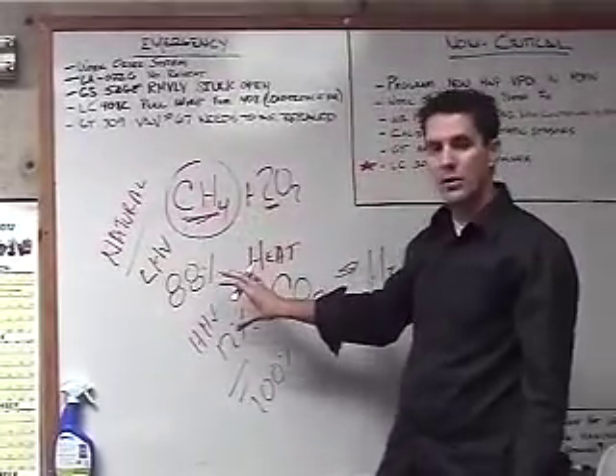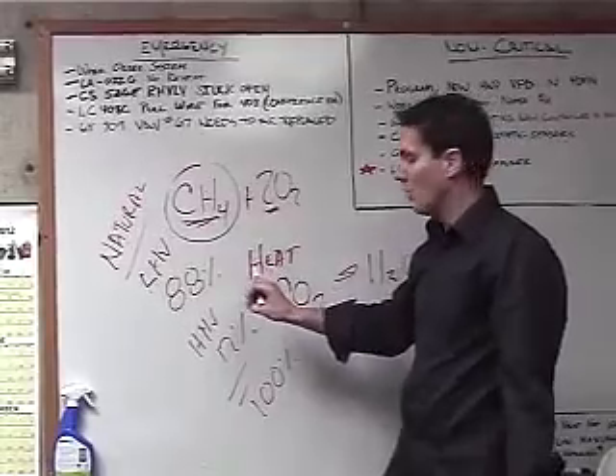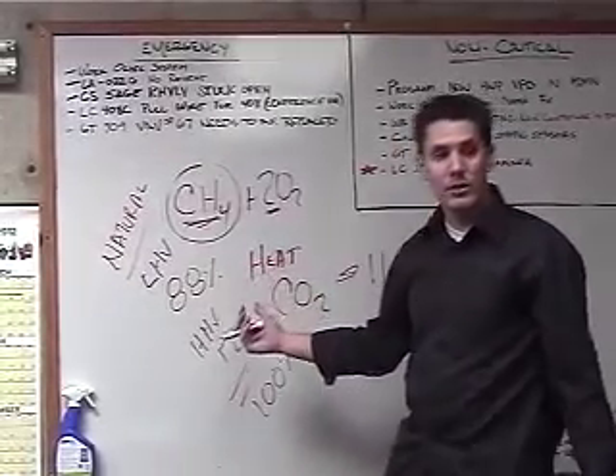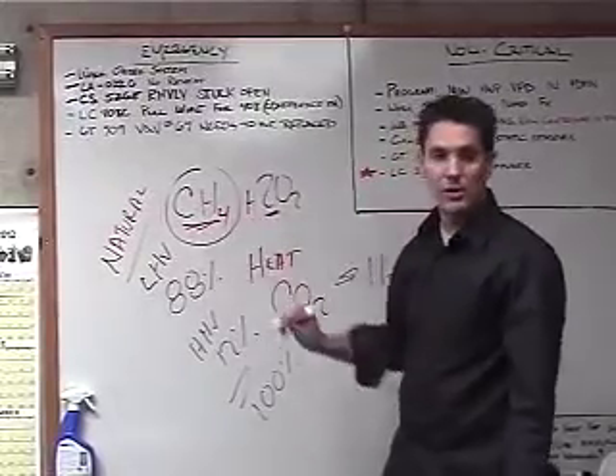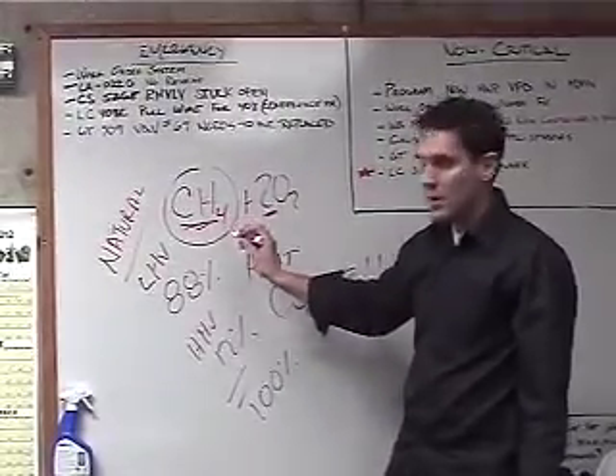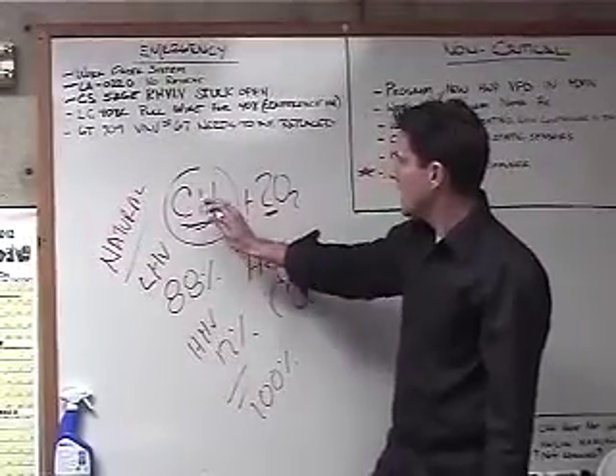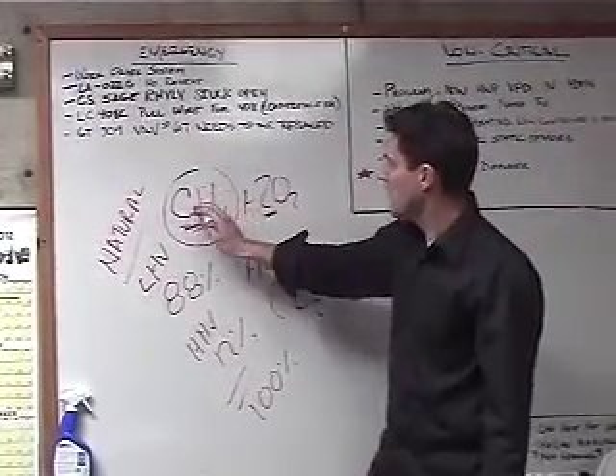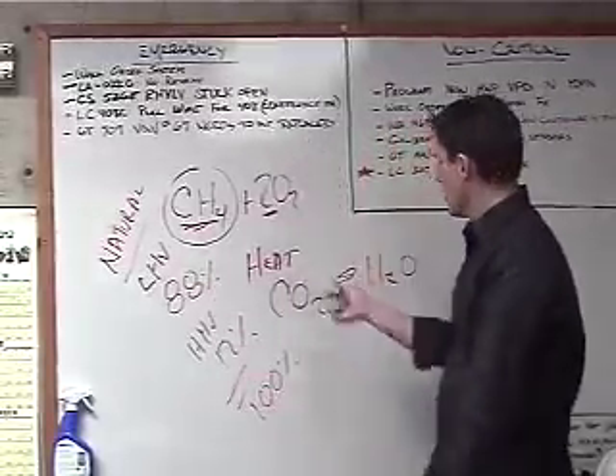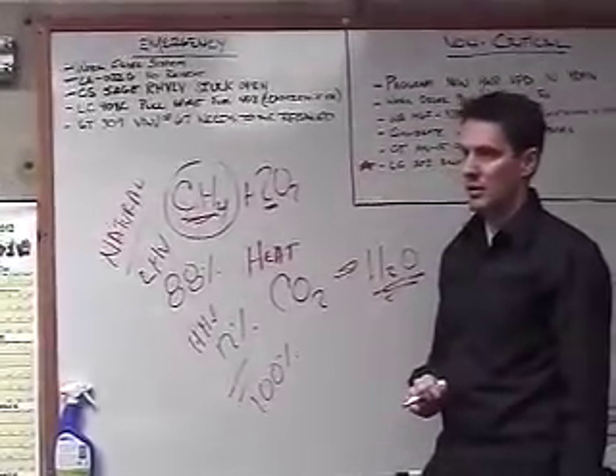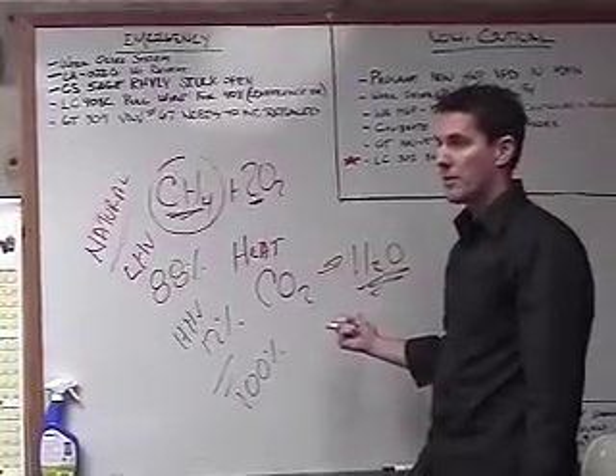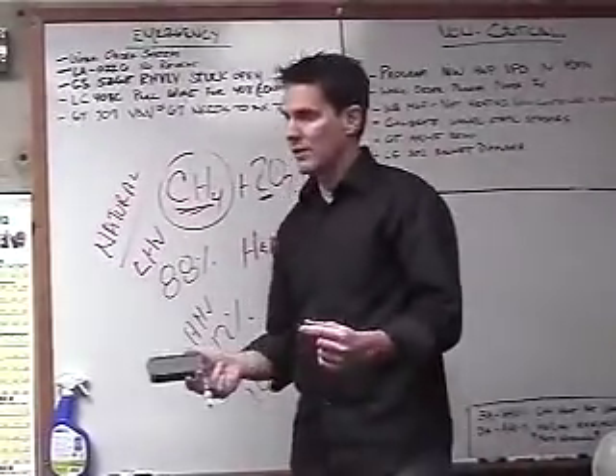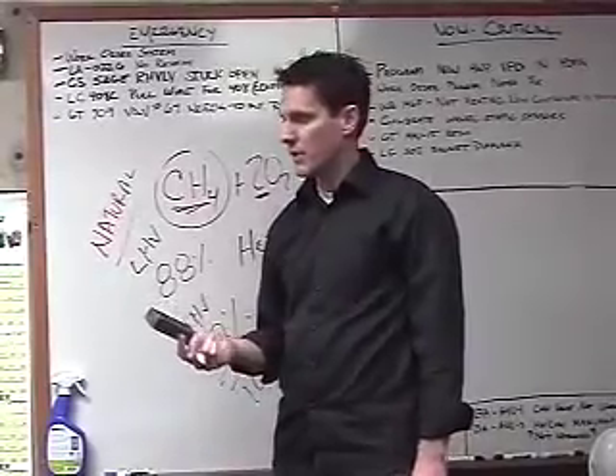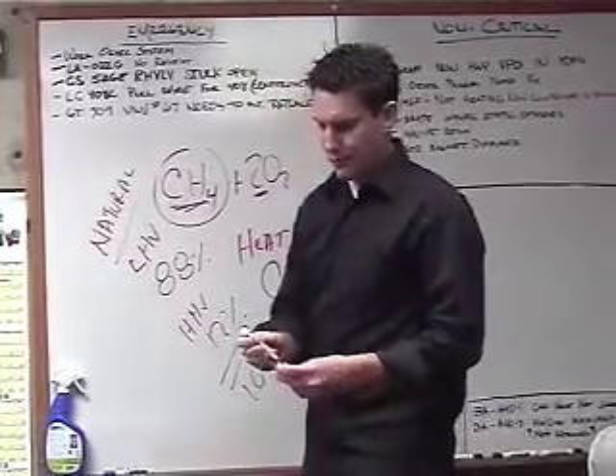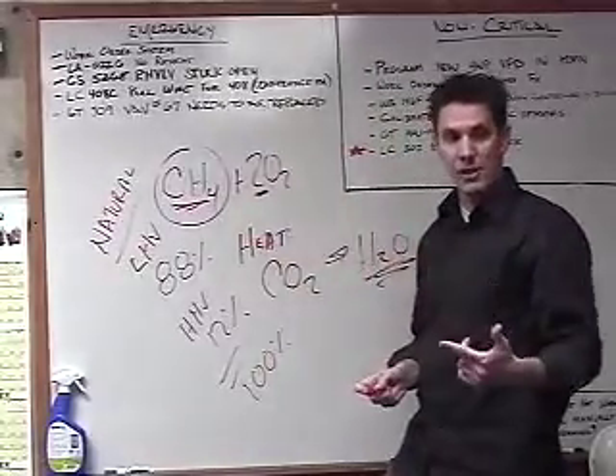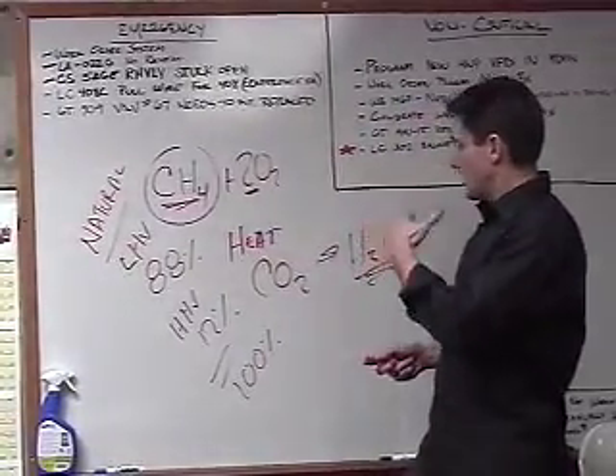This is completely different if you're using propane, or butane, or kerosene, or light oil number 2, because your CH mixture is no longer the same. You don't have the same ratio. So when I have more hydrogens in my hydrocarbon, if this ratio between these two increases, what's going to increase in my process of combustion? I'm going to create more water vapor. Okay, now let's talk about water vapor. You guys run steam on your side? Okay, we just got through teaching a 2-day class up at the University of Utah for their technicians on their steam systems. And we just went through all of this.